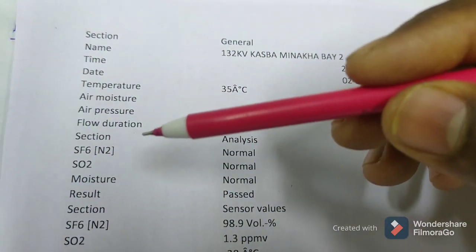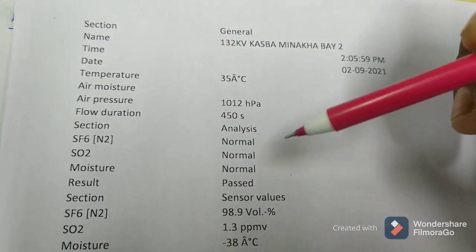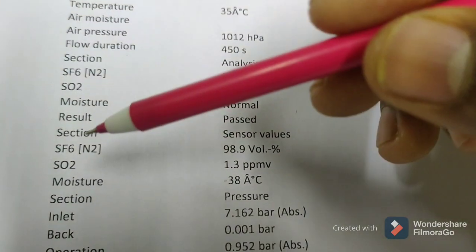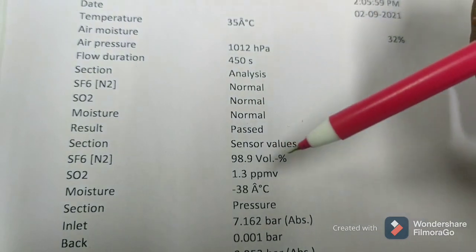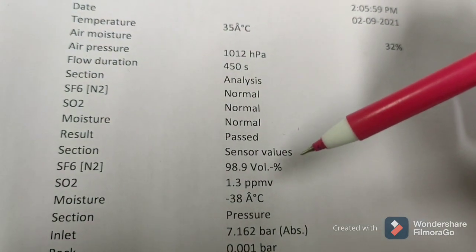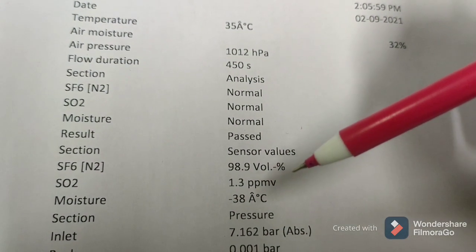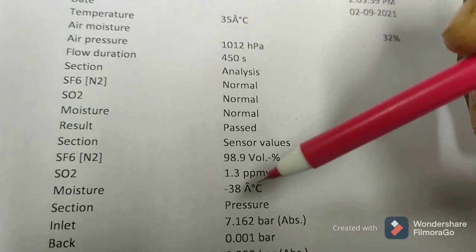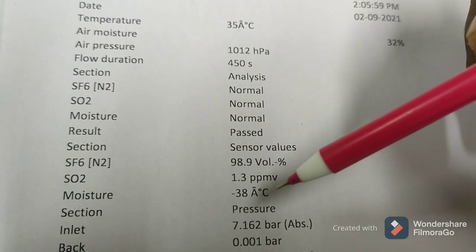we are getting SF6 normal, SO2 normal, and moisture also normal. The result has passed. The SF6 N2 percentage volume is 98.9%, SO2 is 1.3 ppmv, and the moisture is -38°C.